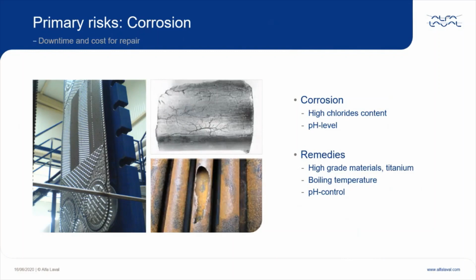One of the best materials to be used for chloride-containing fluids is titanium. The corrosion resistance of titanium can be 10 to 20 times greater than that of corrosion-resistant stainless alloys such as duplex or super duplex, making titanium an ideal material for CLD applications, at least for the heat transfer surfaces where the temperatures are the highest. The plate and frame heat exchangers with the higher thermal efficiency as compared to shell and tube technology provide an affordable choice for using titanium instead of duplex or super duplex, which may, as we'll see later, corrode within a very short time, while the lifetime of the titanium plates will be 10 years or more for this kind of service.